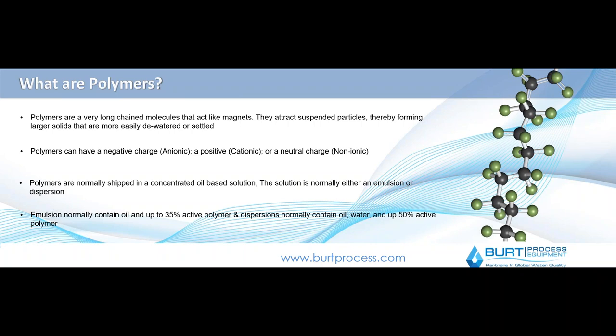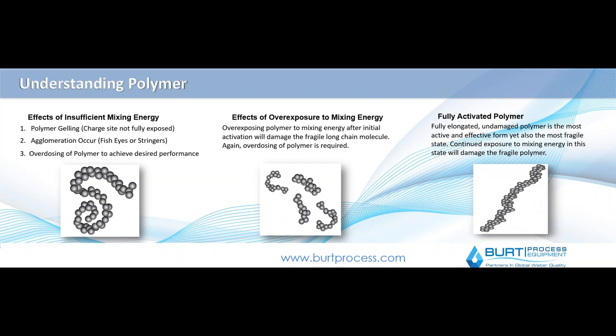Because polymers react with water and the species in water, liquid-based polymers have to be shipped in a medium that allows them to be kept for use — typically an oil-based solution or emulsification droplet, whereby the polymer is emulsified in a small amount of water. In order to really utilize the polymer, these systems have to strip away that oil and then activate the polymer for actual use within your process. That is what they call polymer activation or polymer mixing.